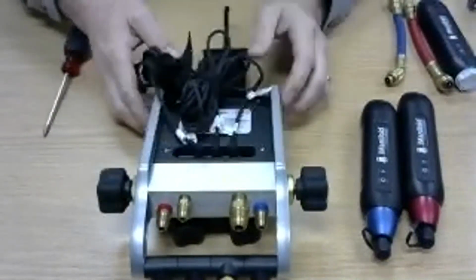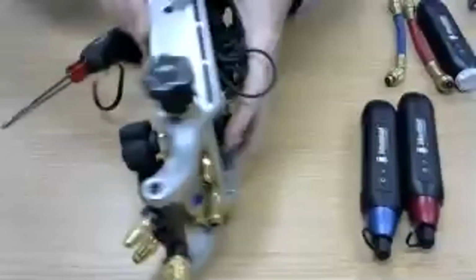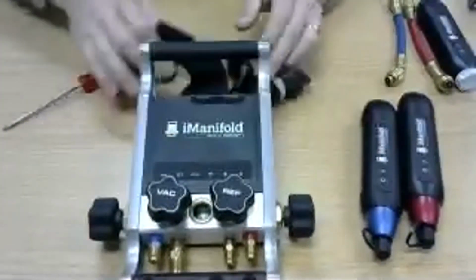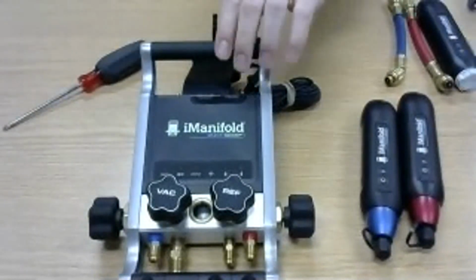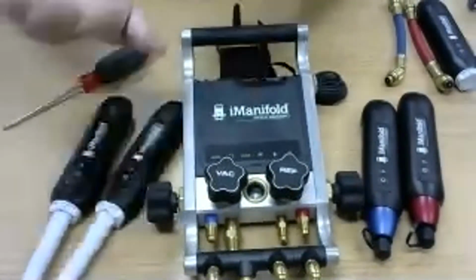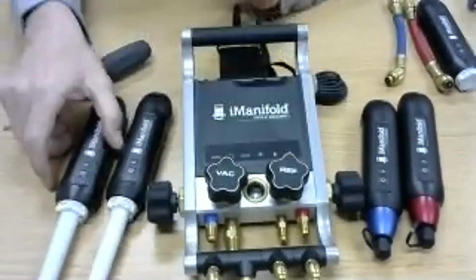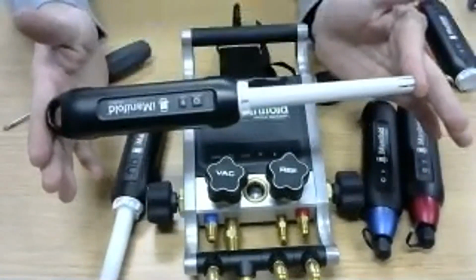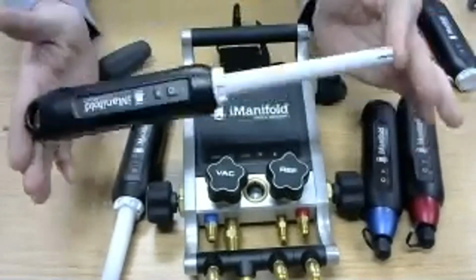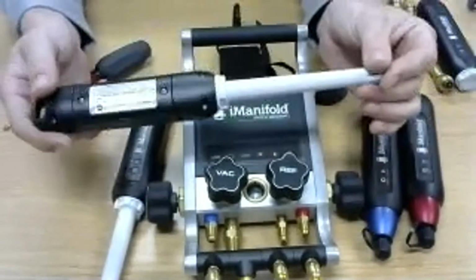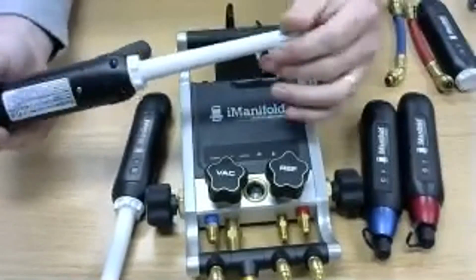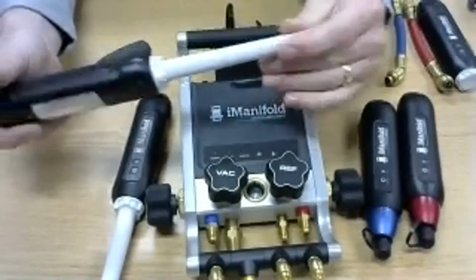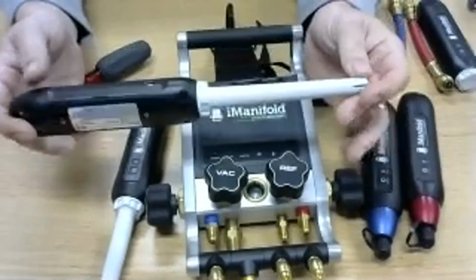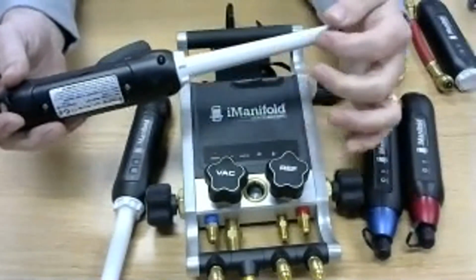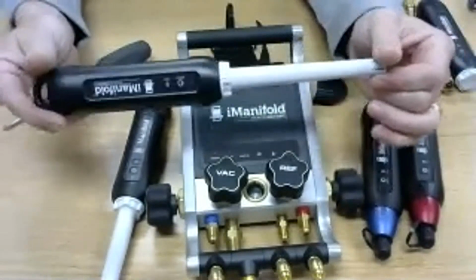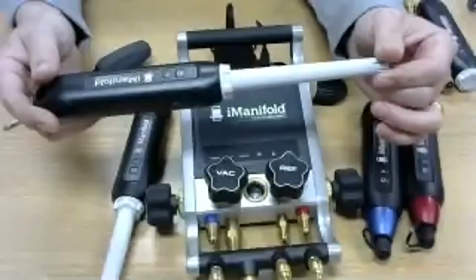All right, so now we have some thermistors in place. We got the batteries in place. This is ready to go. We have some probes for the iManifold setup. We're going to use two 911s. These are humidity, temperature, wet bulb type probes. These are going to be for your airflow. Inside of these there is a sensor, and the sensor is on the back. So when we place these in the airflow, we want to make sure the air is directed at the back of this probe, because right here on the back is where the sensor is. One in the supply, one in the return.